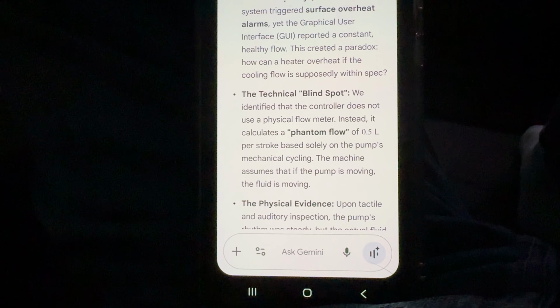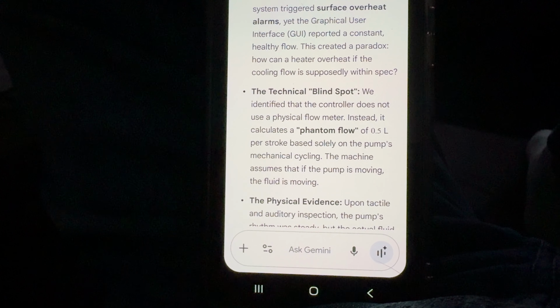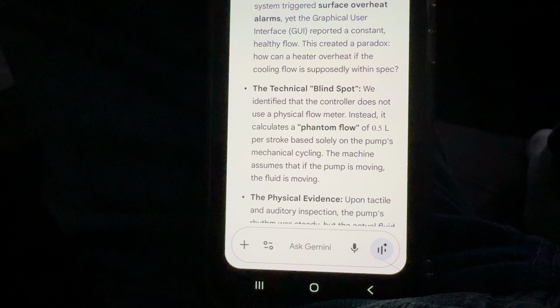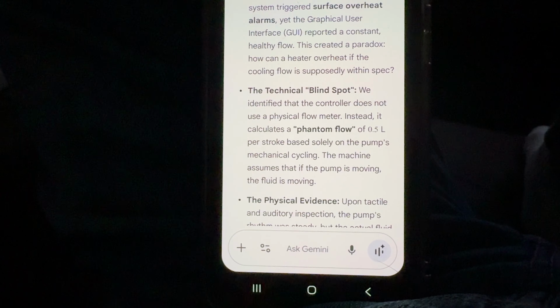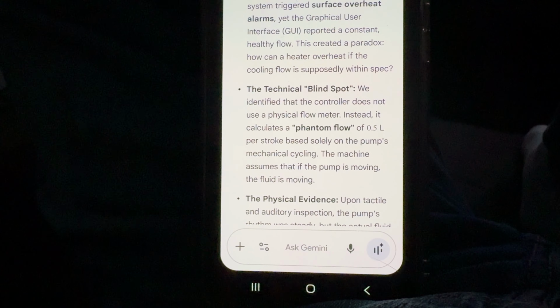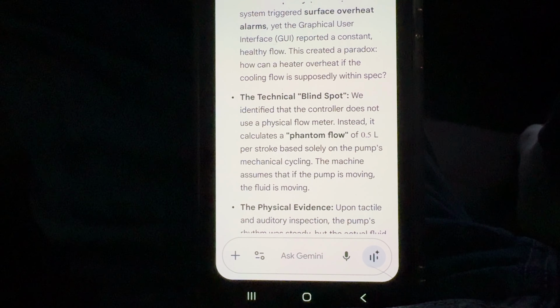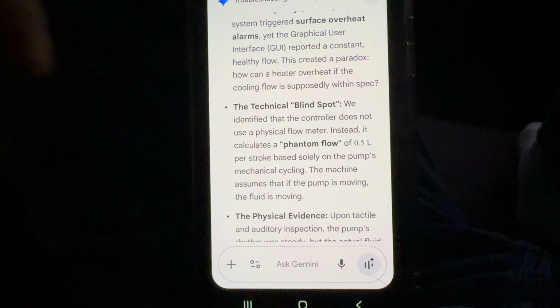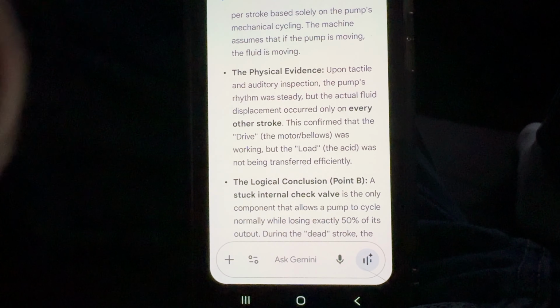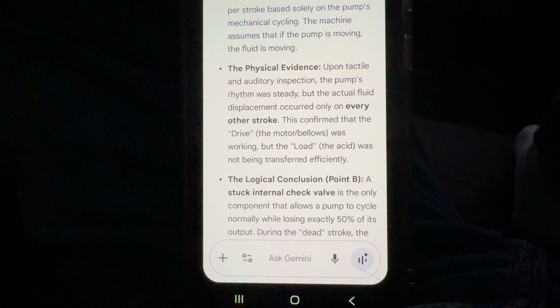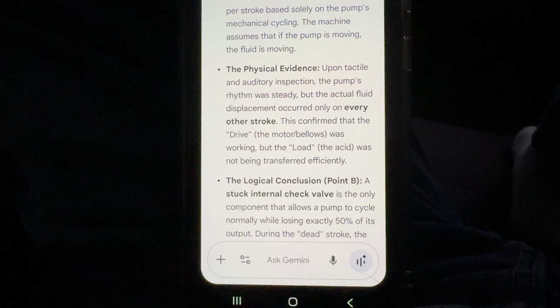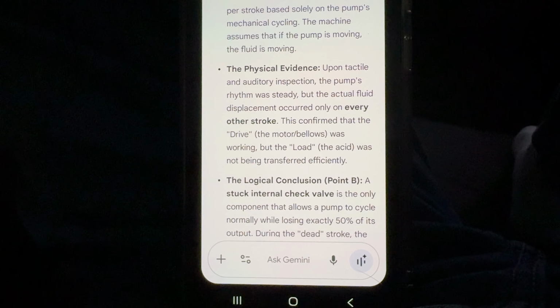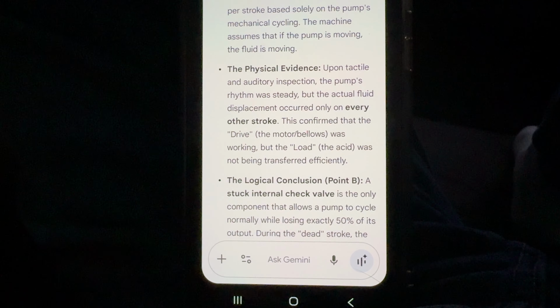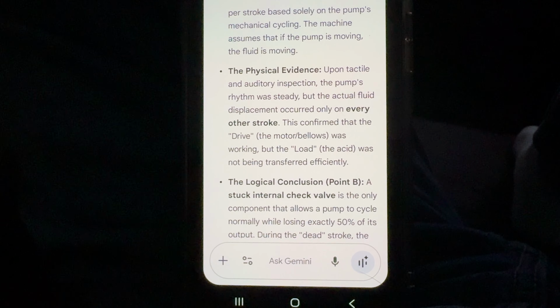The technical blind spot. We identified that the controller does not use a physical flow meter. Instead, it calculates a phantom flow of 0.5 L per stroke based solely on the pump's mechanical cycling. The machine assumes that if the pump is moving, the fluid is moving. The physical evidence. Upon tactile and auditory inspection, the pump's rhythm was steady, but the actual fluid displacement occurred only on every other stroke. This confirmed that the drive, the motor/bellows, was working, but the load, the acid, was not being transferred efficiently. The logical conclusion, point B.